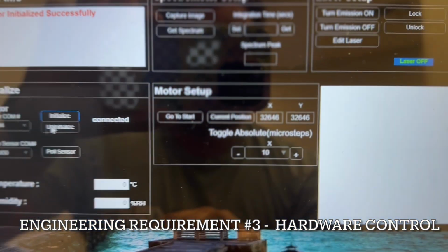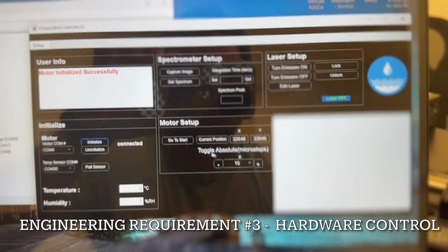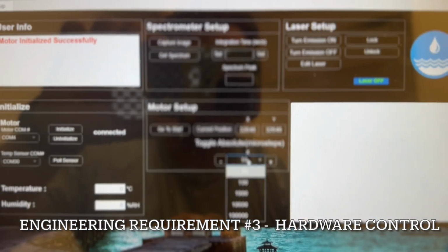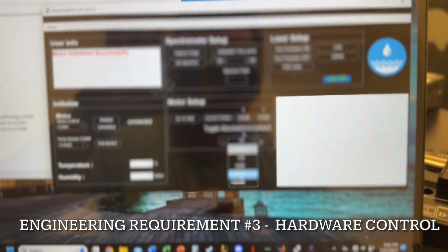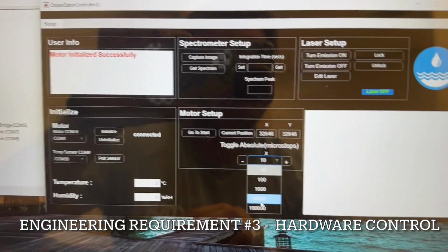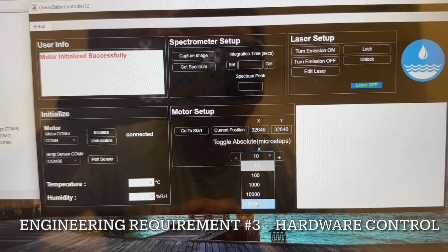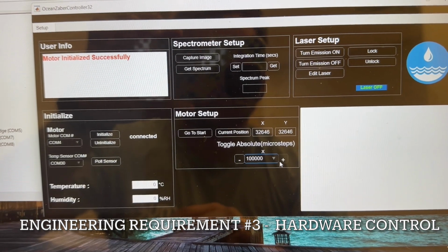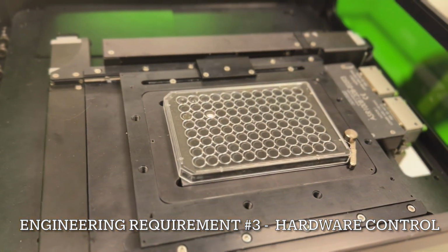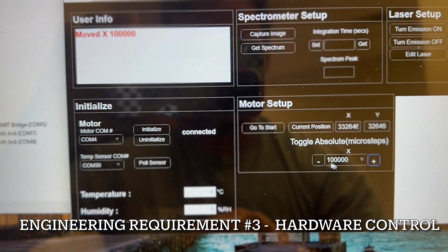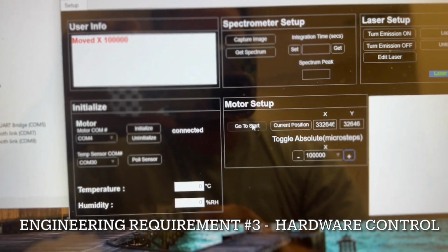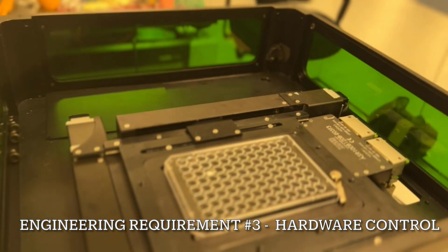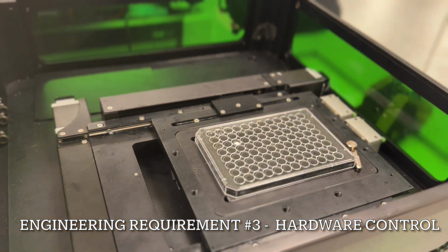The motor is controlled by this area. What I'm going to do is change this to 100,000 microsteps, because that's the equivalent of one whole well. That's 1, 2 wells, 3 wells, and so on and so forth. And when I want to go back to the original well, I hit go to start, and there we go.